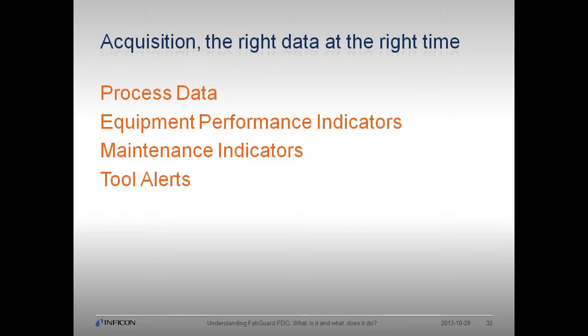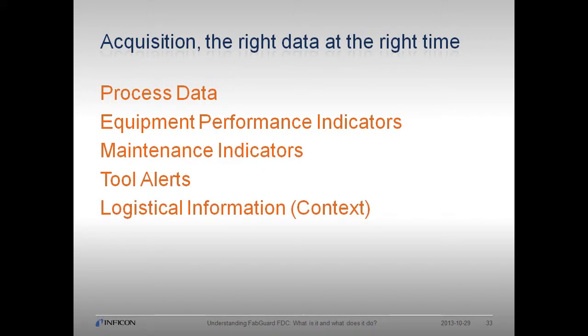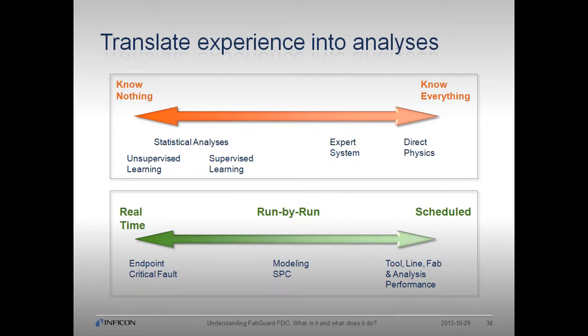FabGuard can also acquire and analyze alarms and events that happen on the equipment, and these alarms can be analyzed using a Pareto report. For wafer processing, FabGuard can collect any context or logistical information available, such as Lot ID, Slot ID, Substrate ID, Process Job, Recipe, etc. From a knowledge perspective, you can go from knowing nothing to knowing everything about a process.